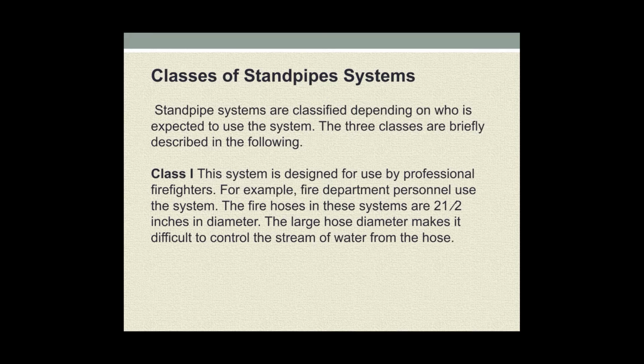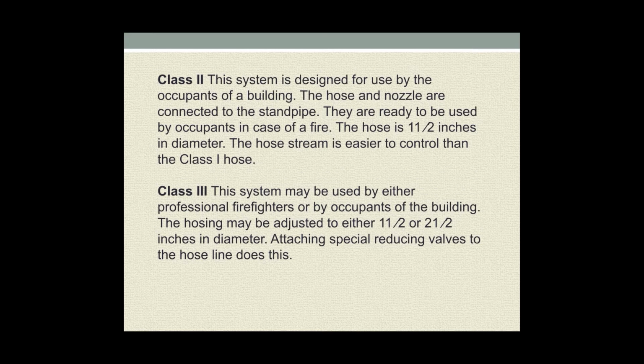Classes of standpipe system. Standpipe systems are classified depending on who is expected to use the system. The three classes are briefly described in the following. Class 1. This system is designed for use by professional firefighters. For example, fire department personnel use the system. The fire hoses in this system are 2 1/2 inches in diameter. The larger hose diameter makes it difficult to control the stream of water from the hose.